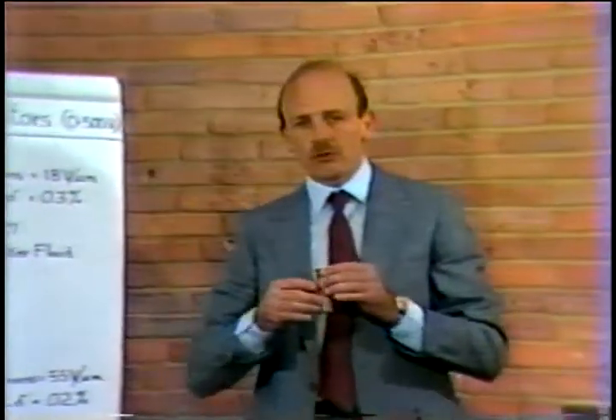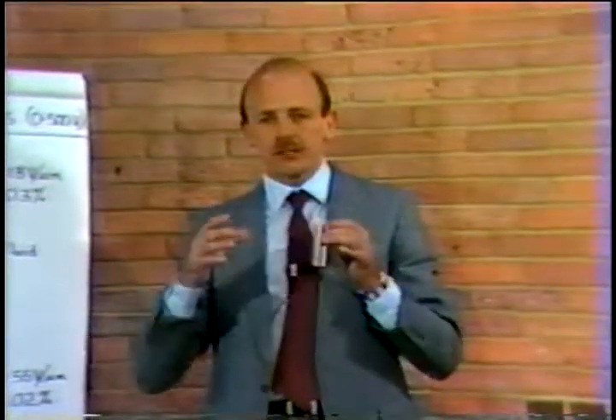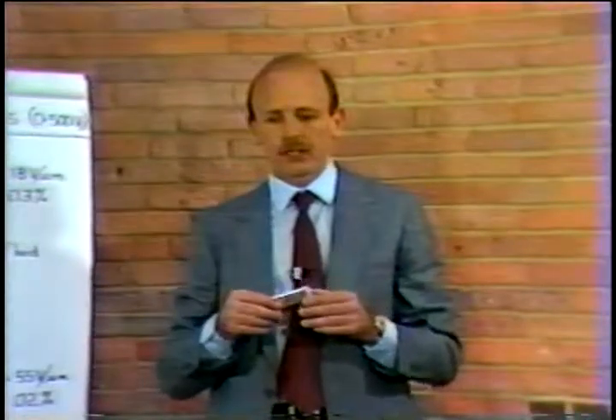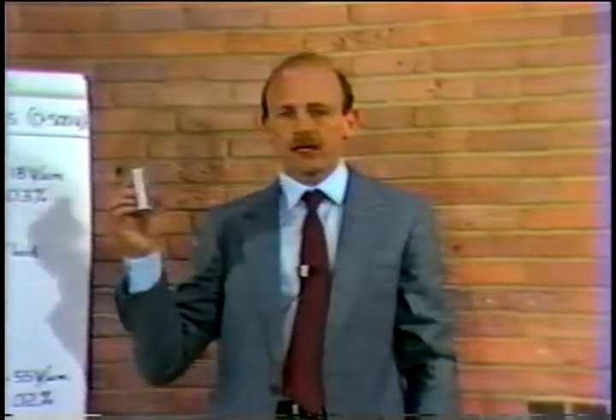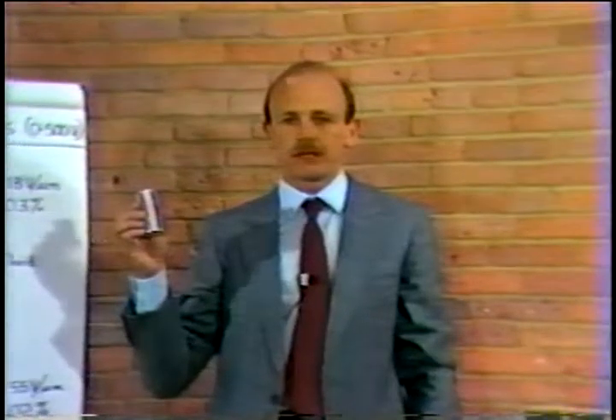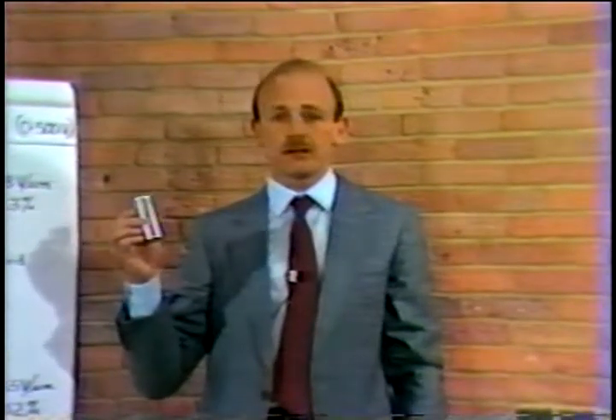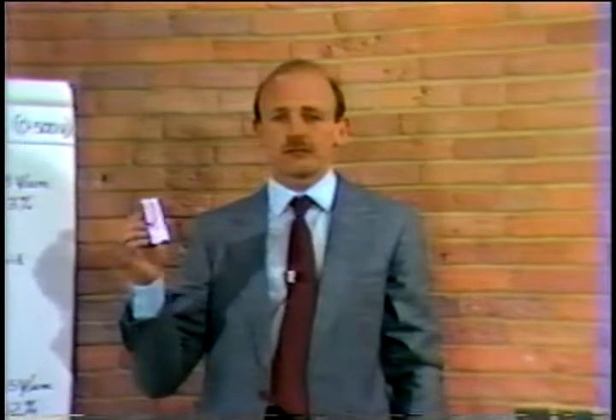It's further observed that during thermal cycling, the roll will expand and the outer part of the roll will become loosened. And as it contracts, it will stay in a loosened form. Voids can develop in the outer parts of these rolls. And at high voltages, especially above 500 volts, partial discharges become very important. Here we plot the change in capacitance that occurs due to partial discharges as a function of time on life test.